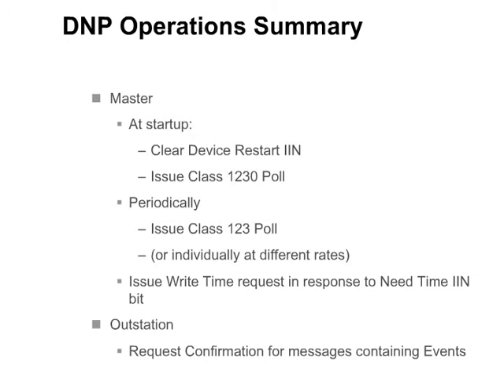The test results are color-coded in both columns to highlight tests that have passed or failed. This slide provides a summary of normal DNP operations. On startup, the master clears the device restart IIN indication in the outstation and issues a Class 1230 poll. This poll will retrieve all buffered events and the current static data in order to initialize the master's database.